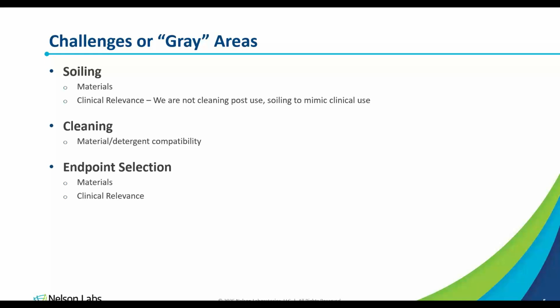So when it comes to soiling, something to consider is the material of your 3D printed device. In my experience, some materials like to soak in the test soil, so we need to consider what kind of test soil to use. And the other challenge is clinical relevance. For these devices, we're not necessarily going to be cleaning post-use. This cleaning validation is performed prior to the initial use.